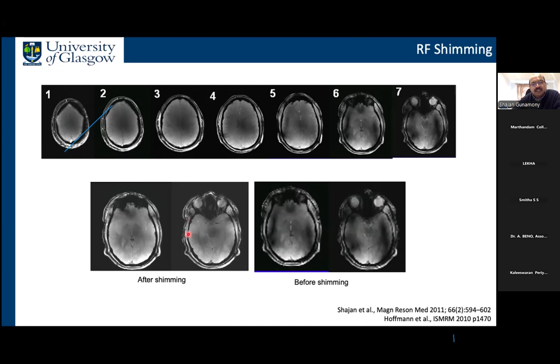So here you see the image that is produced by this coil. In the upper slices of the brain, it's quite okay, but you see in slices 6 and 7 that it is quite inhomogeneous. And that is before shimming, in the initial circularly polarized mode. Now we can calculate and apply a phase, which will remove these dark spots, and then we get a much more homogeneous image. So that's the image before shimming, and that's the image after shimming.